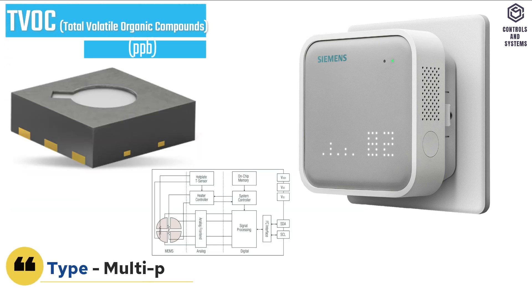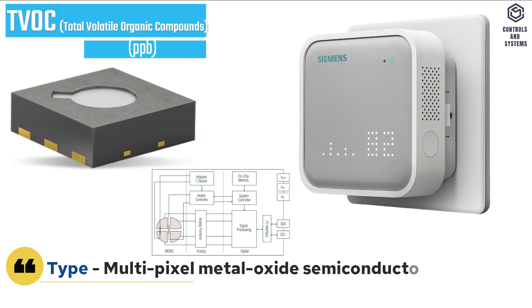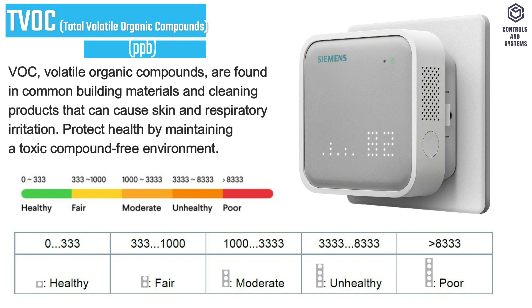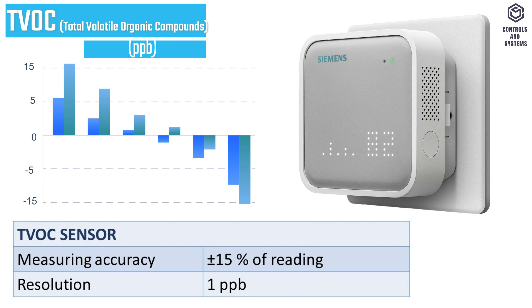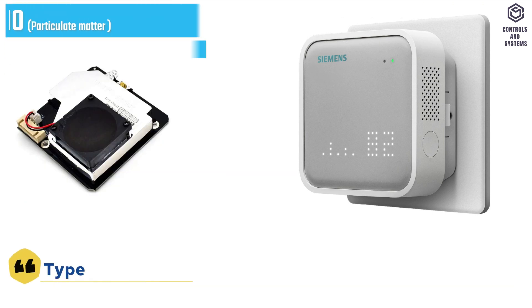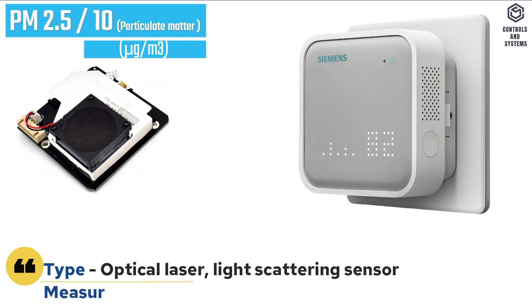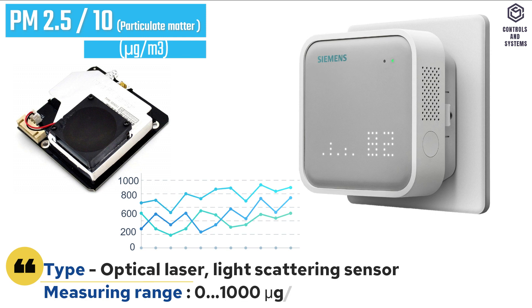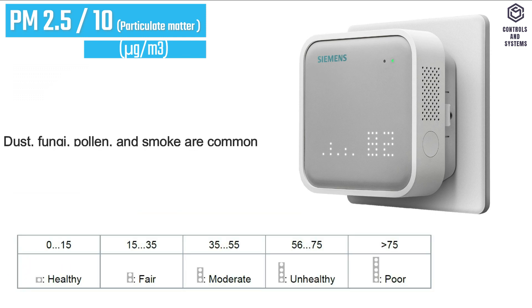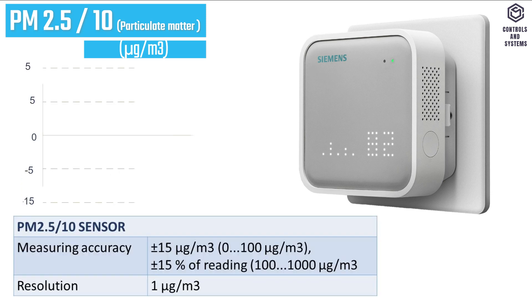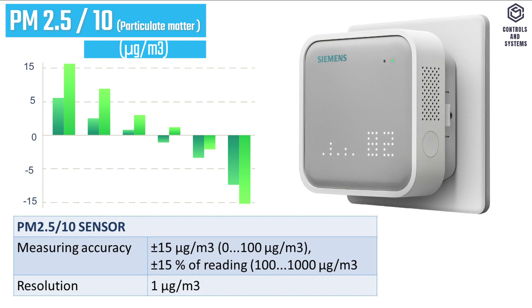TVOC sensor type is a multi-pixel metal oxide semiconductor sensor, measuring range 20 to 36,000 ppb. The TVOC range will depend on the number of LED counts shown in the table. PM2.5 sensor type is an optical laser light scattering sensor, measuring range 0 to 1000 micrograms per cubic meter. The PM2.5 range will depend on the number of LED counts shown in the table. Measuring accuracy and resolution are shown in the table.